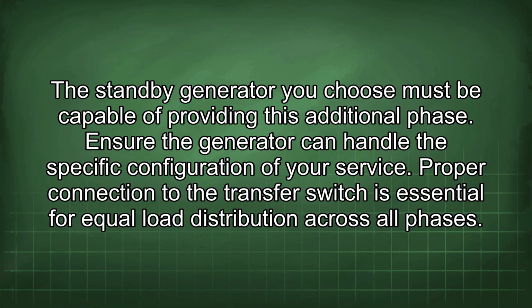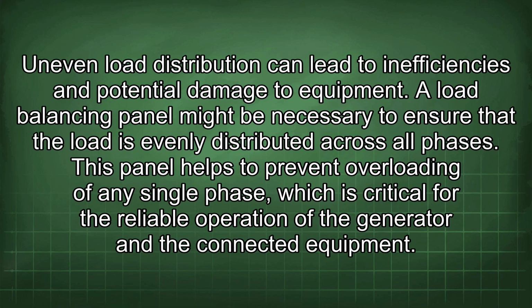Proper connection to the transfer switch is essential for equal load distribution across all phases. Uneven load distribution can lead to inefficiencies and potential damage to equipment. A load balancing panel might be necessary to ensure that the load is evenly distributed across all phases.